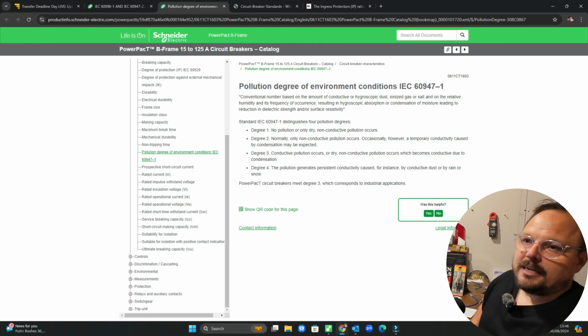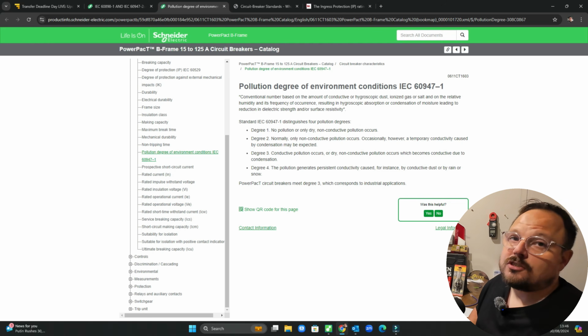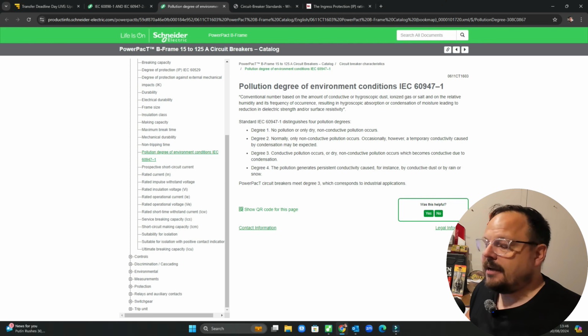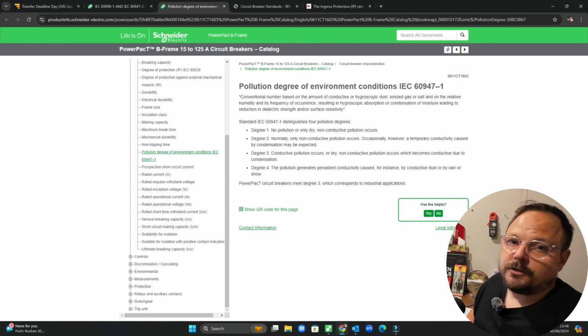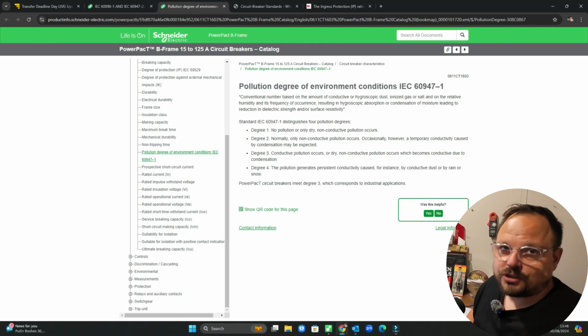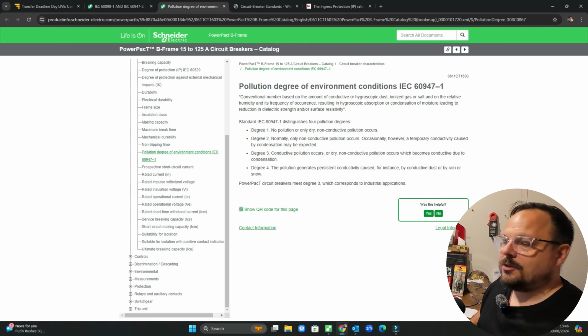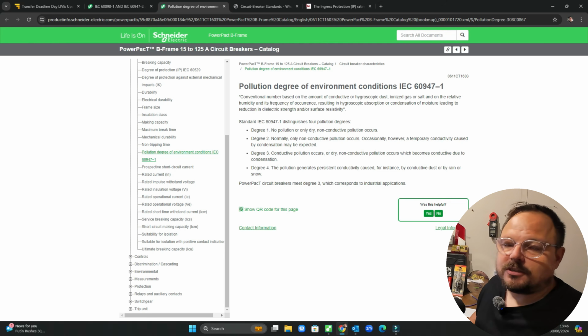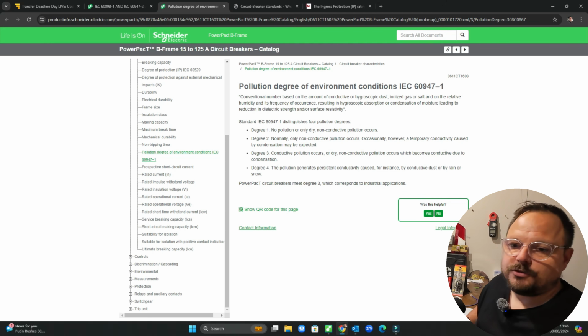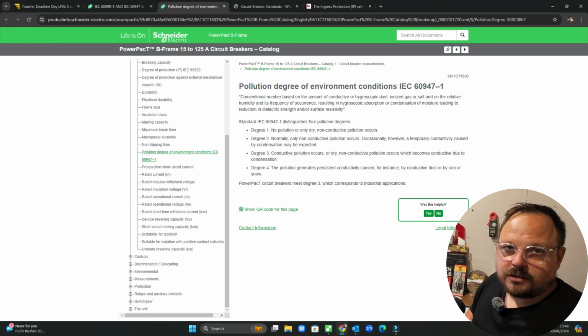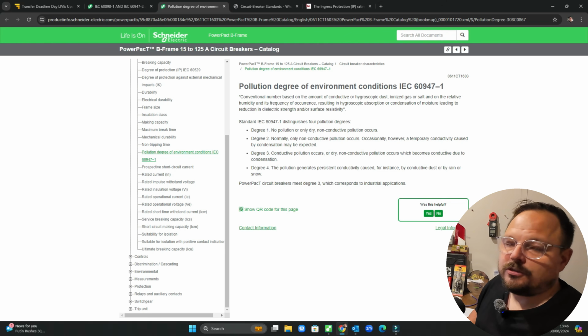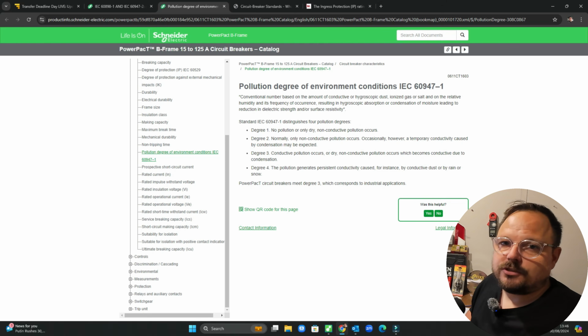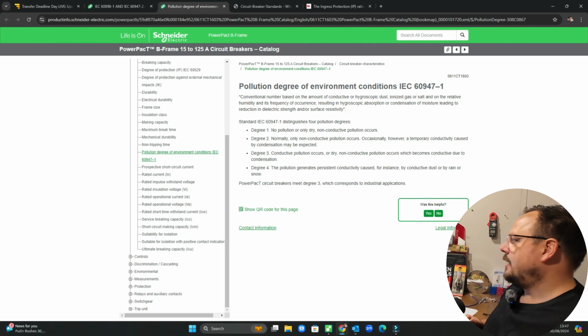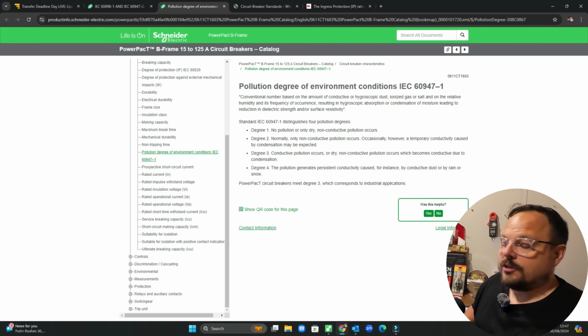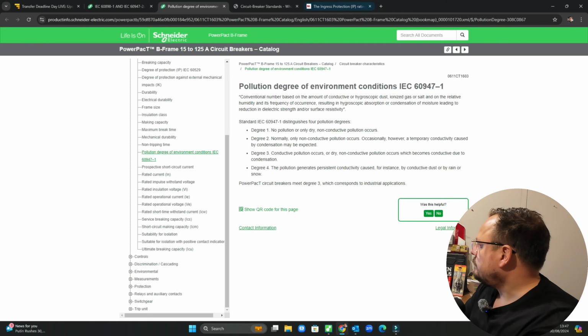So if you've got one of these on the outside of a dwelling, for example, at some stage in the course of a year in nearly every part of the UK, it will be exposed to extreme dust and snow. There could be times when users need to go and interact and operate with them. So all of this nonsense around the doors being open and closed and all the rest of it to form a different type of pollution degree area is a joke, and that is something that is quite misleading and shouldn't be getting pushed out into industry as acceptable, because it isn't. So yeah, that kind of explains what those are. We'll come back to that at the end of the video.